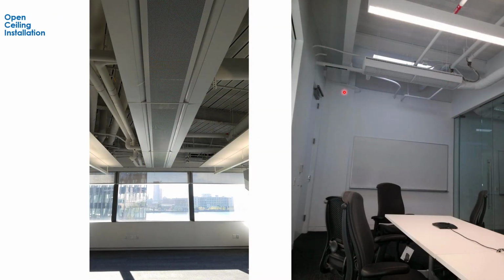Now here are some examples of open ceiling concept chilled beam applications. So this is a finished chilled beam. This is a Swegon Adriatic beam. The conditioned air comes out through these slots on the side. The return air comes in through the grill on the bottom. And this has been left in an open ceiling concept. You can see that this is a 2-pipe system. Here are the water lines coming over, and then they're using flex connections. You can even see the ball valves for isolating this.